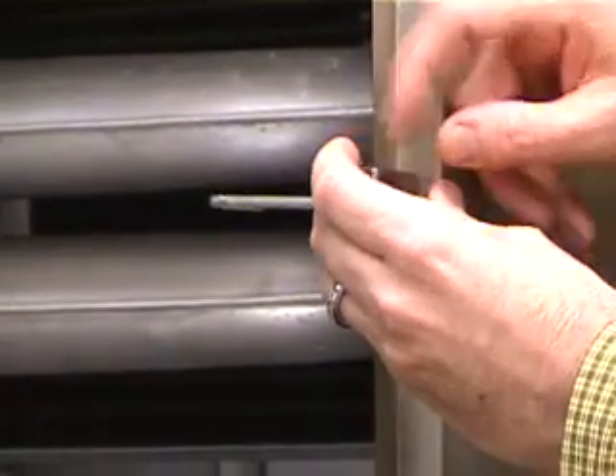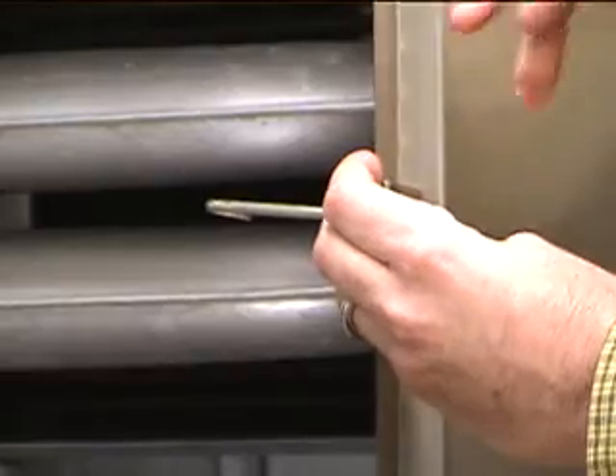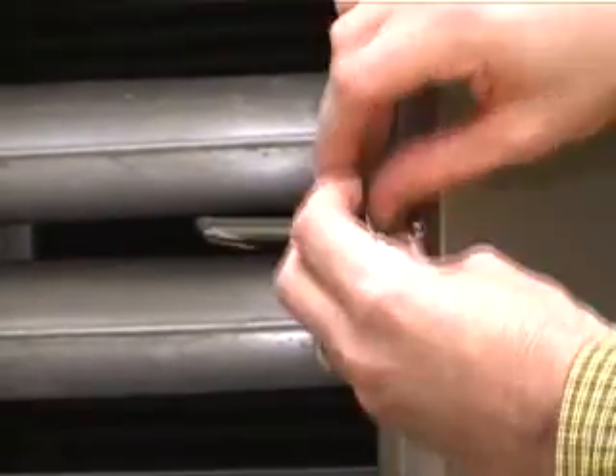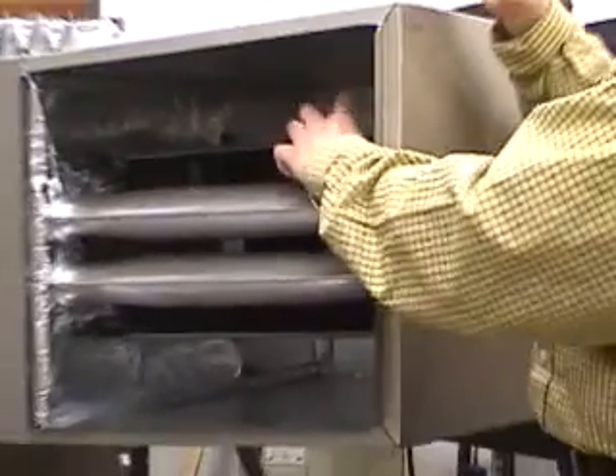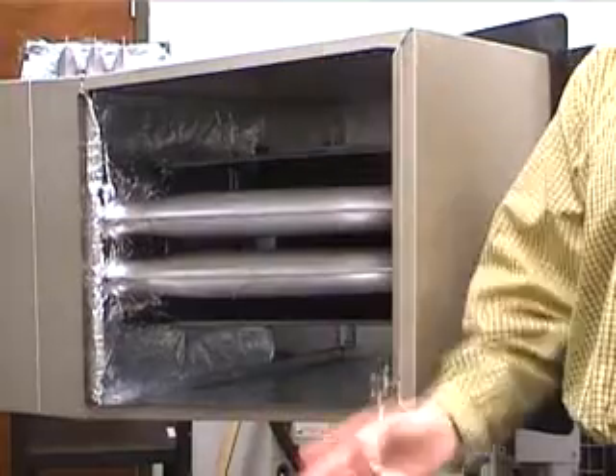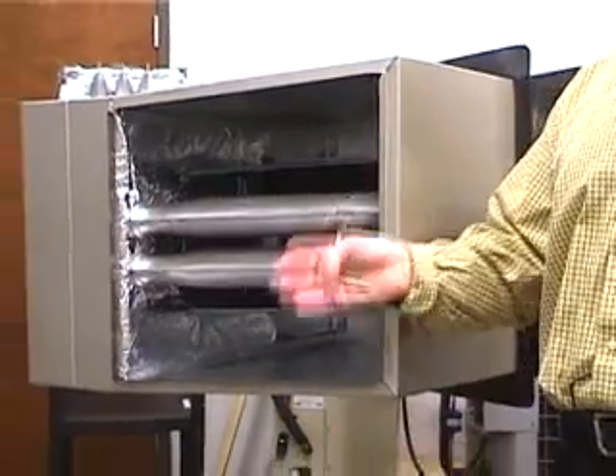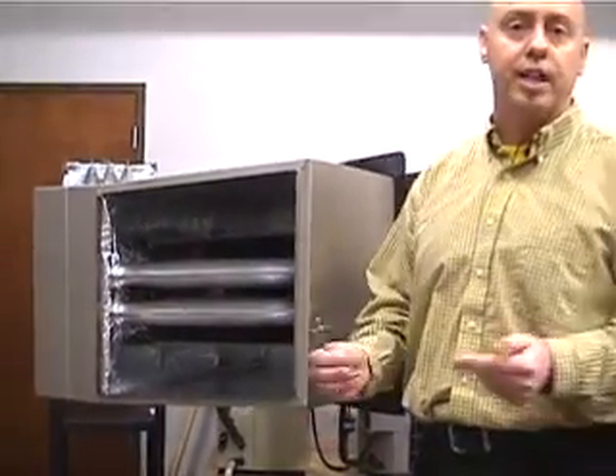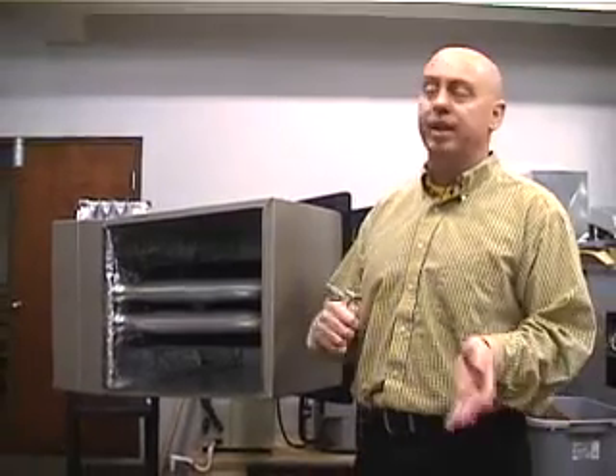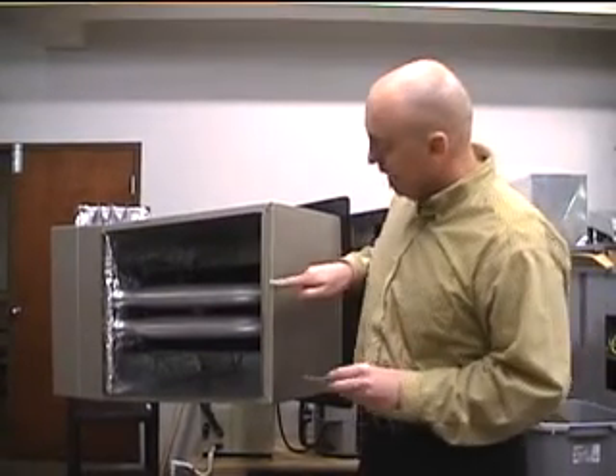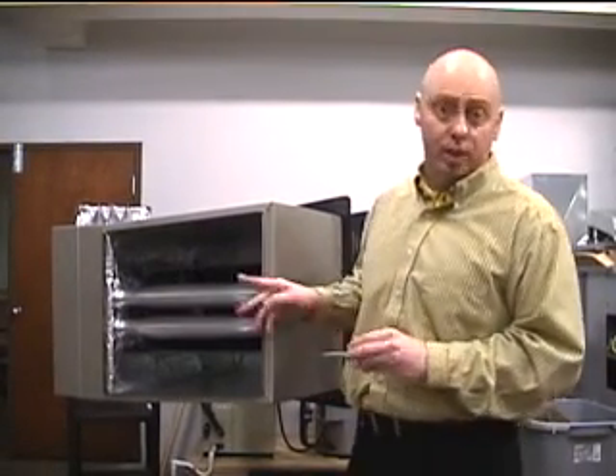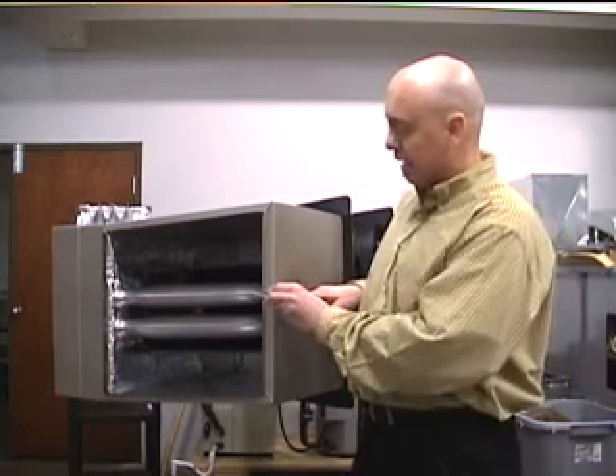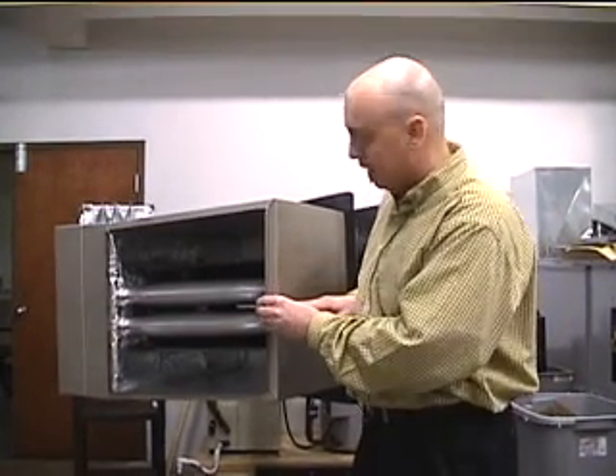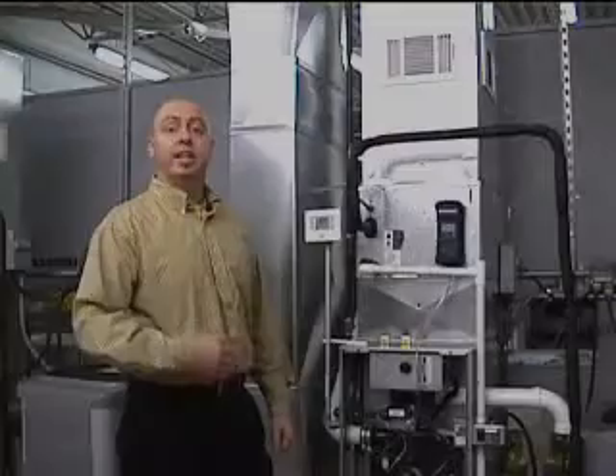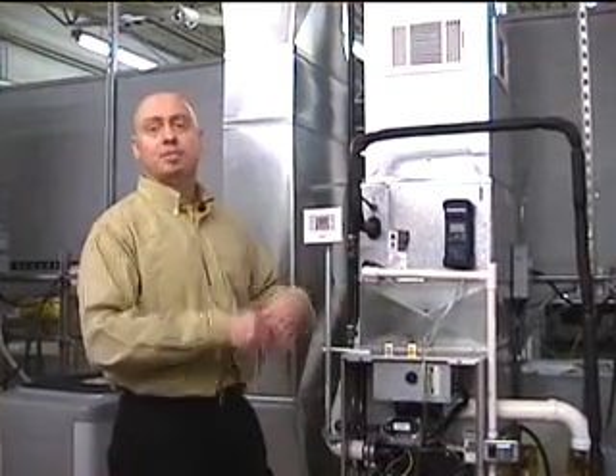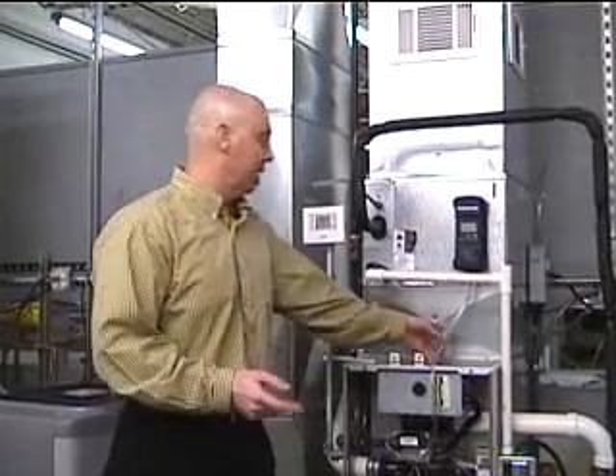So then the probe will actually sit here, and since I'm looking for pressure that's inside the cabinet, that actually works fairly well. You don't want to be on the sides, because on the sides there's typically baffles, and they could run all the way up the side of the furnace. They are to keep the heat on the outside chambers of the heat exchanger, and they can give you some very false readings that way. But as long as you stay close to the top and don't drill in really far, you can easily tap the back of the furnace like this and get your static probe in there. Getting familiar with checking pressure drops, static pressure, things like that, you can learn a lot about the system.